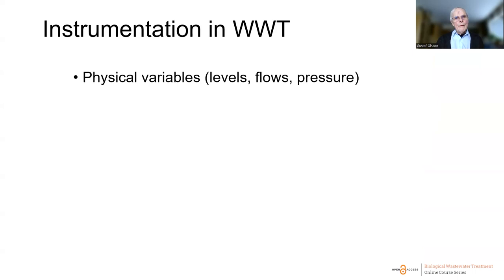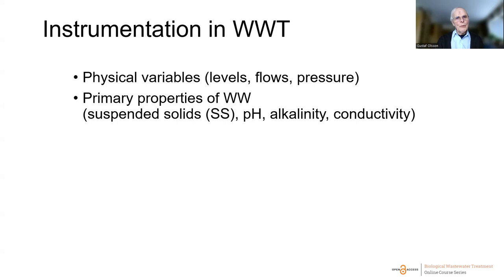Looking at instrumentation for wastewater treatment, there is a whole sequence of different measurements. Physical variables like levels, flows, and pressure are monitored to keep the plant running — they don't directly reflect process behavior, but without them we wouldn't be able to run the plant. We also need to measure primary properties of the wastewater like suspended solids, pH, alkalinity, and conductivity — these are physical-chemical measurements, not measuring biological activity in itself.